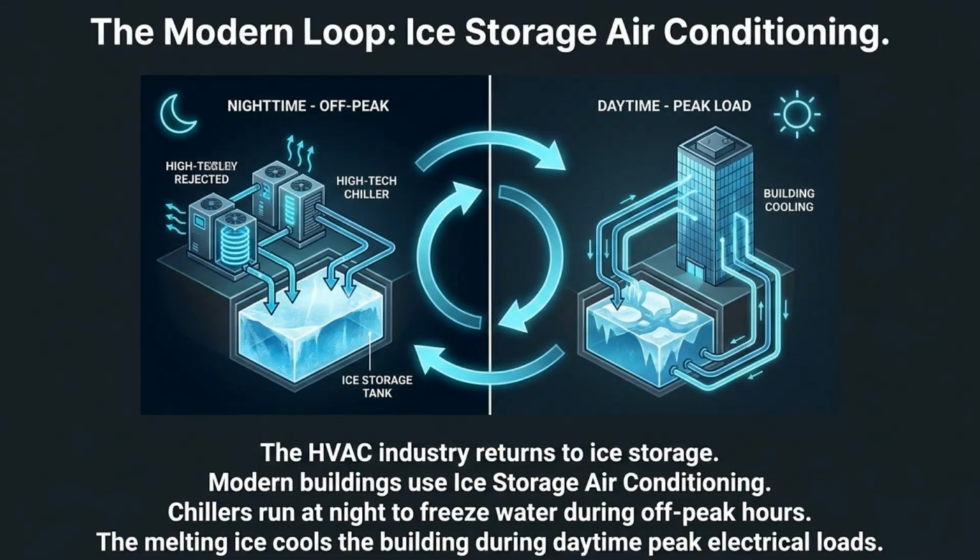The HVAC industry has returned to ice storage air conditioning. Chillers run at night to freeze water during off-peak hours. The melting ice then cools the building during daytime peak electrical loads.